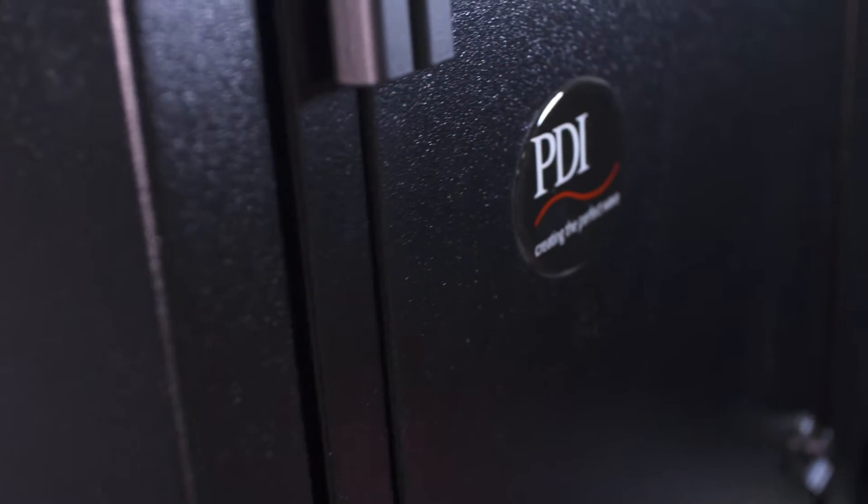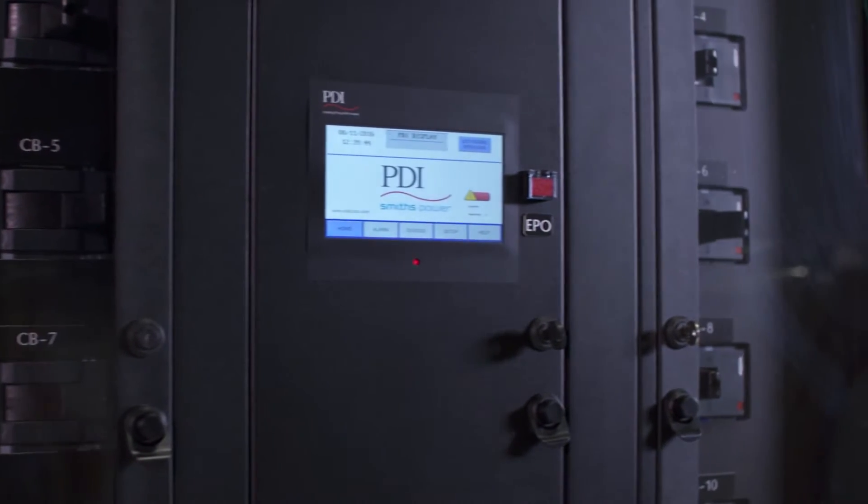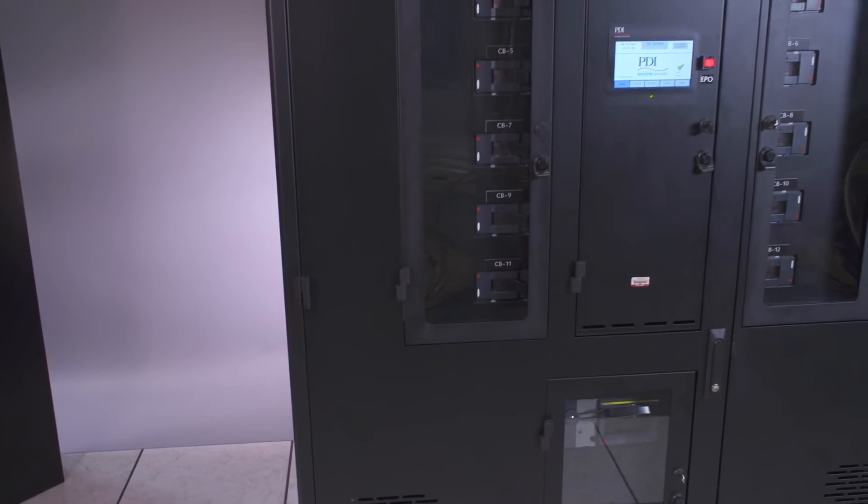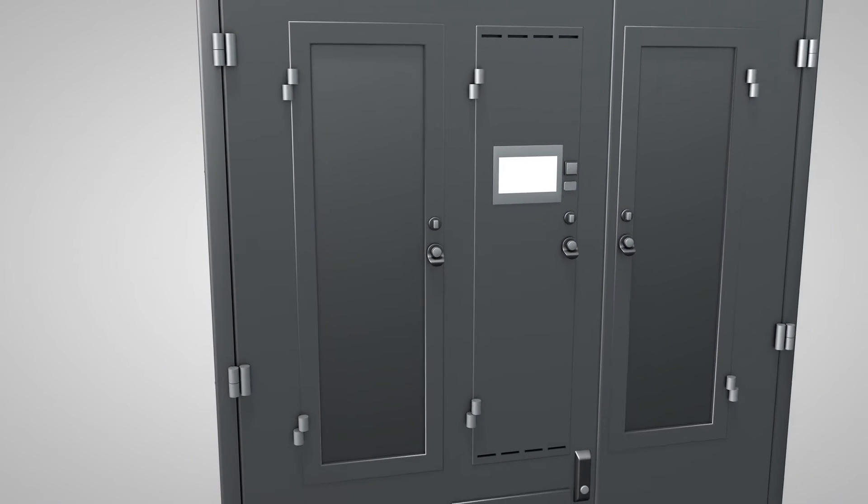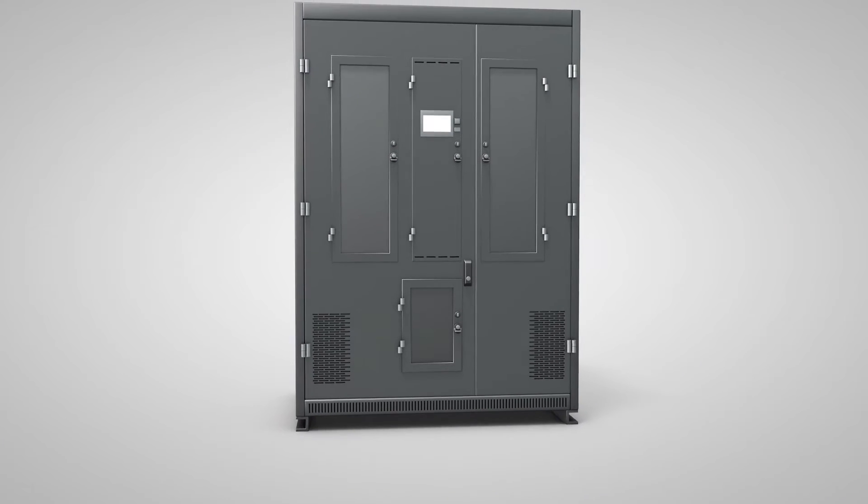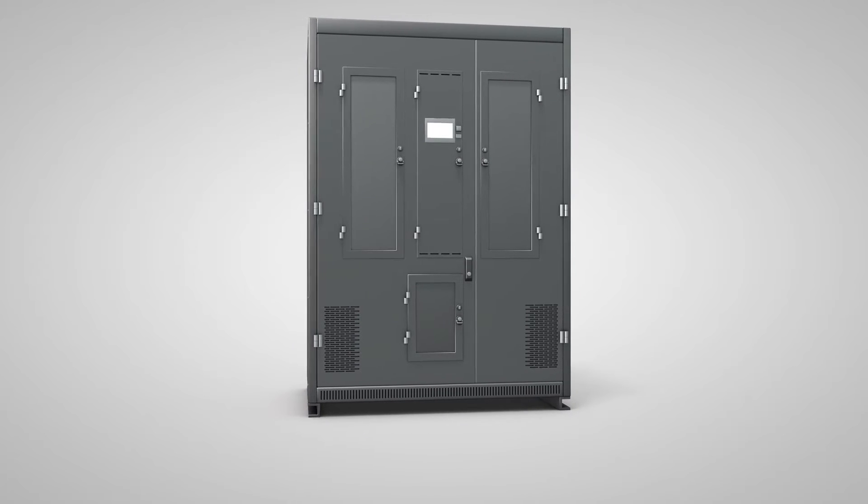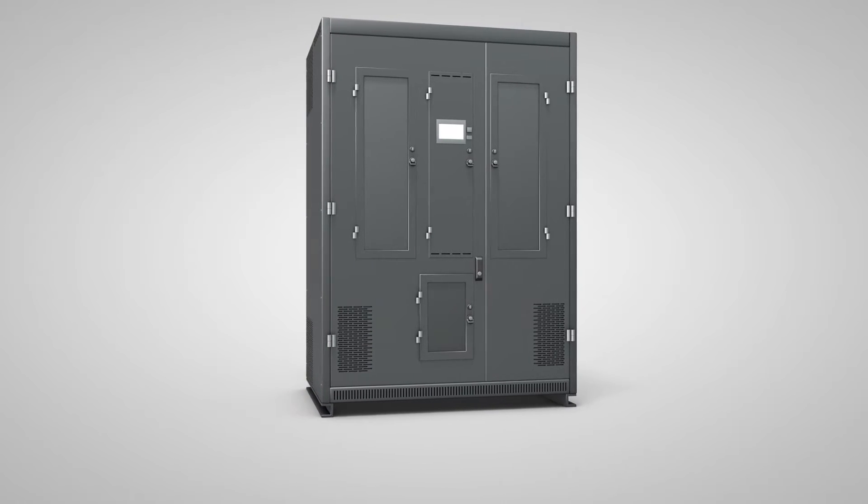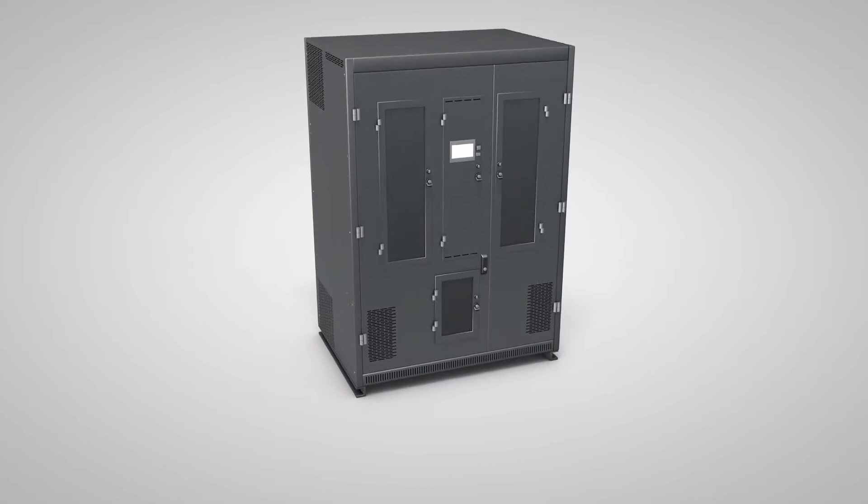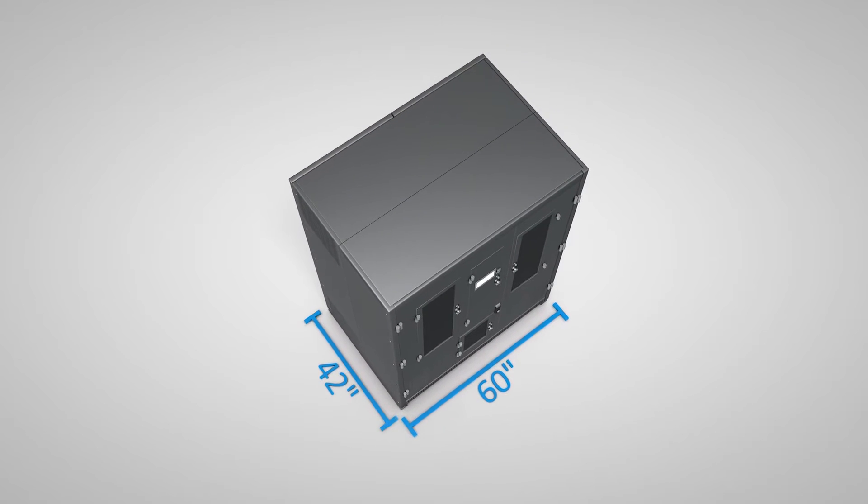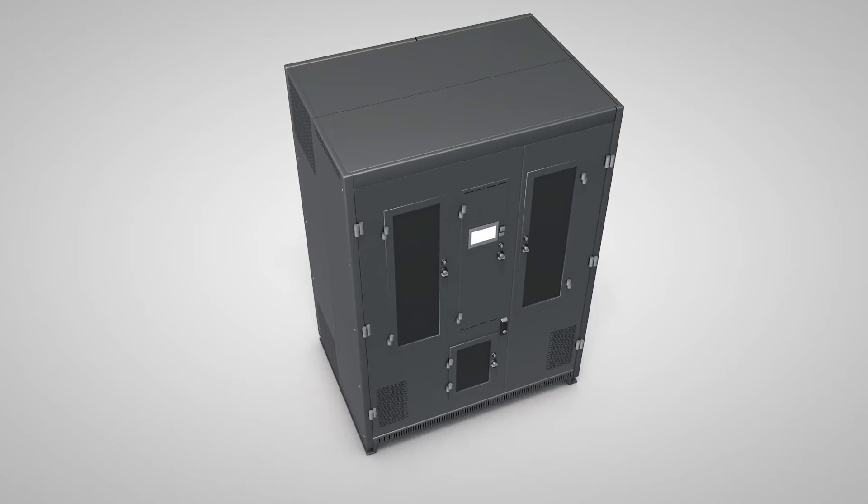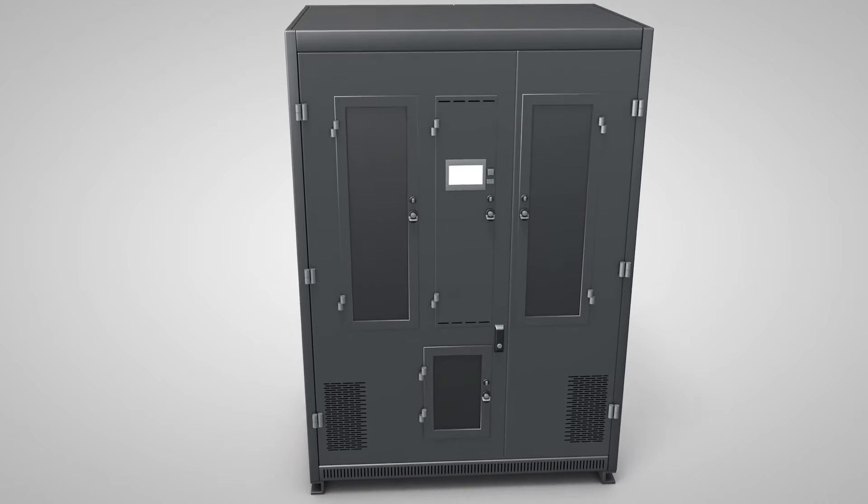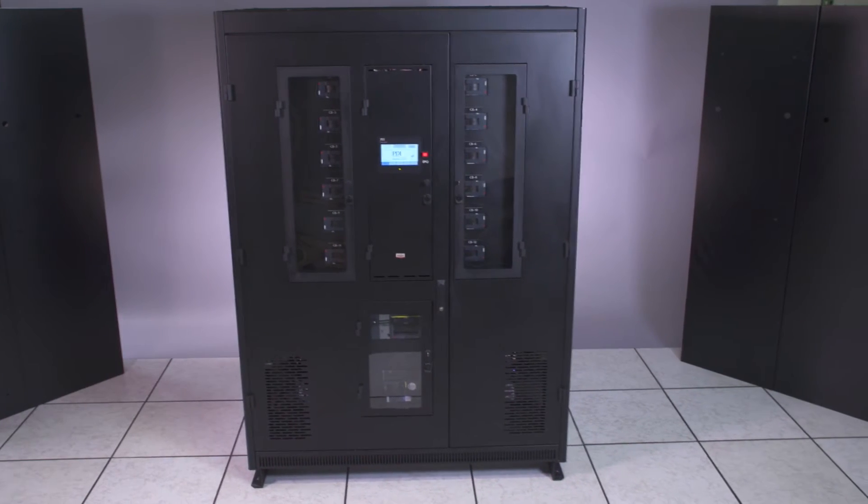One of these products is the PowerHub 2 PDU. Known for its centralized bus design, the PowerHub 2 PDU provides intelligent and flexible power distribution. It accommodates a DOE 2016 high-efficiency transformer from 375 kVA to 1 MVA while maintaining front access and a cabinet size starting at 60 by 42 inches. This reduced footprint allows operators to minimize the space required for power transformation and distribution.